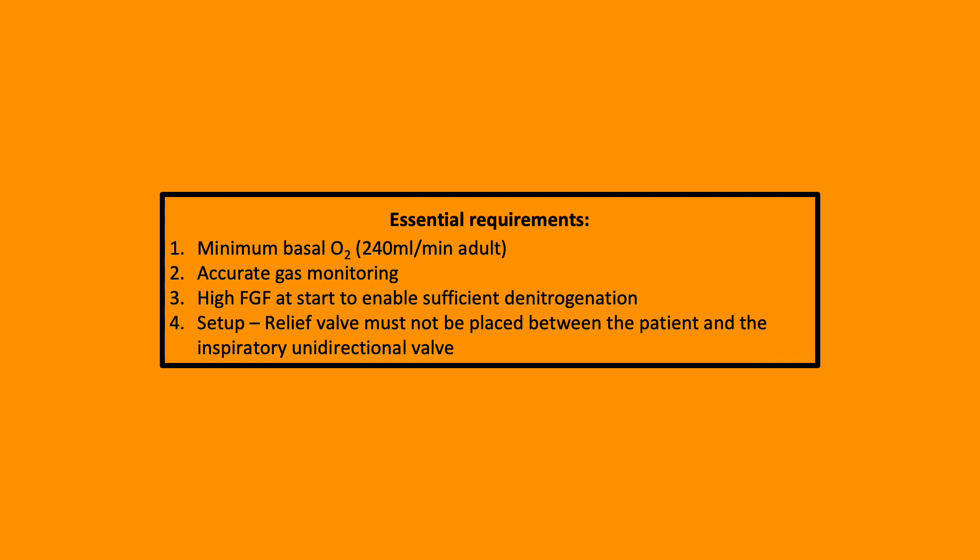Setup factors: The relief valve must not be placed between the patient and the inspiratory unidirectional valve.